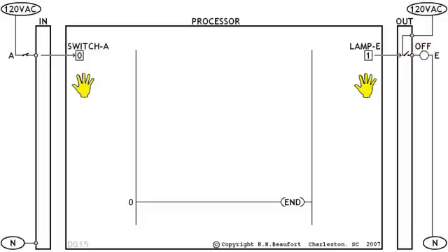Now things like this wouldn't happen in a perfect world, and they don't happen in many beginner level PLC classes either. That's because some instructors don't even mention this type of stuff, even though it's critical to fully understanding PLCs. Let's make sure that we recognize the problem. Notice that the switch is closed in the field and electrical current is flowing, but the bit contains a zero instead of a one. And understanding that discrepancy could be critical in certain beyond beginner troubleshooting situations. The output bit contains a one, which should turn the output in the field on, but the output in the field is still off. So we have another discrepancy that could be important once you leave the beginner level behind. And with the boot camp approach, that's usually less than an hour into the course.